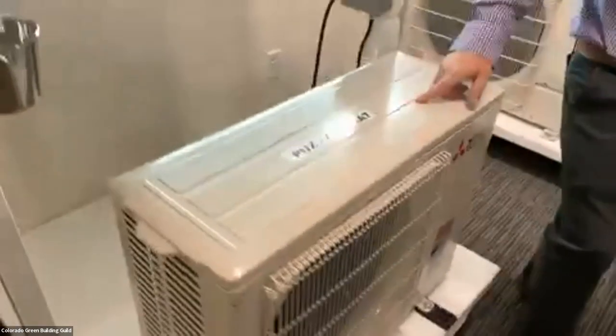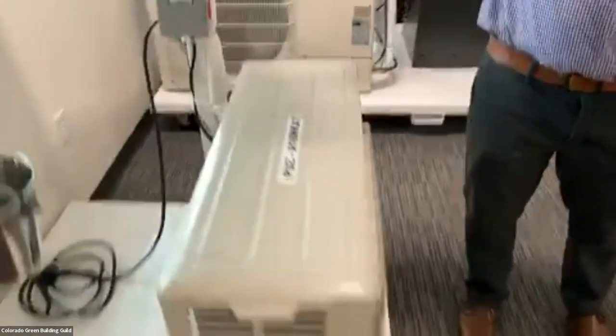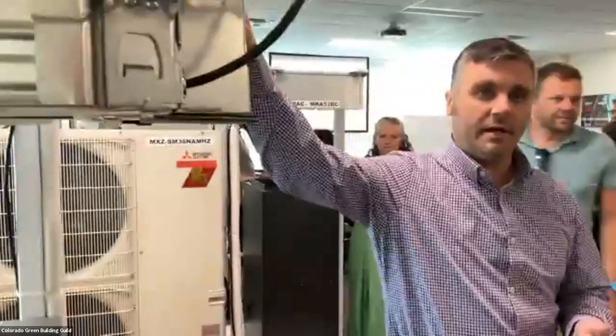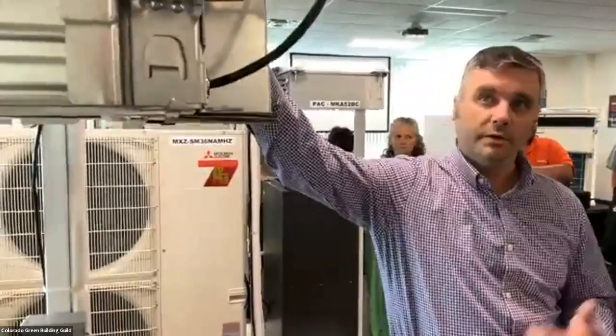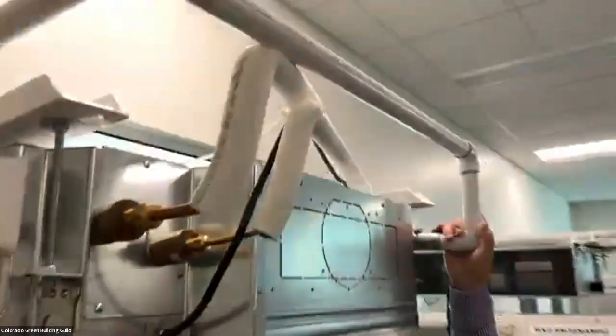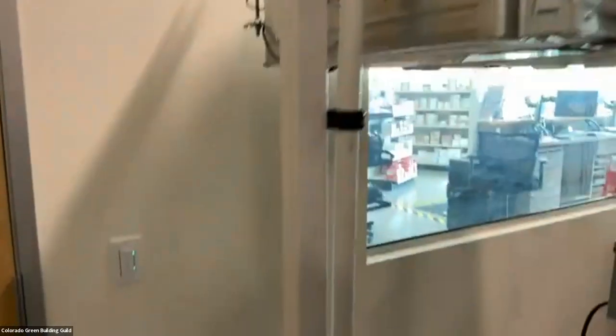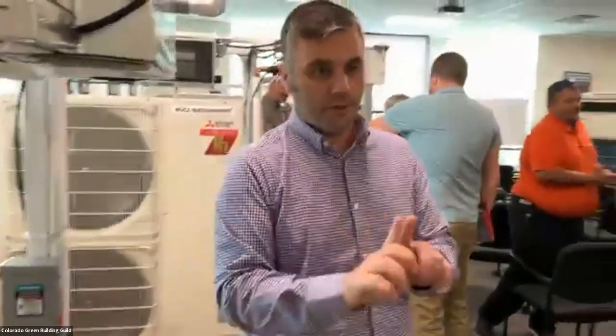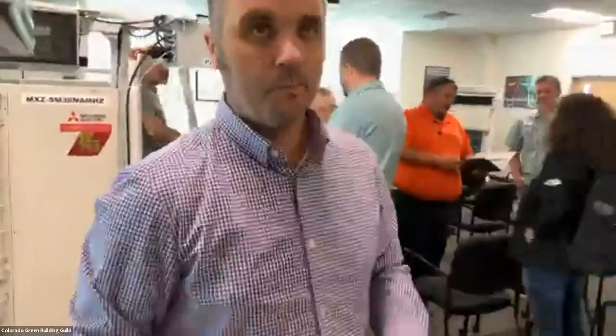This one's set up in a one-to-one application, heat pump or straight air conditioning. It has its own lift mechanism for condensate. You put your condensate tubing right here. It's got about 21 inches of lift and will drain out. No accessories needed. You can set the vanes to work in four directions, two directions, three directions, or one direction. You can put it in the hallway and service this way, or put it in the other room and service that way.